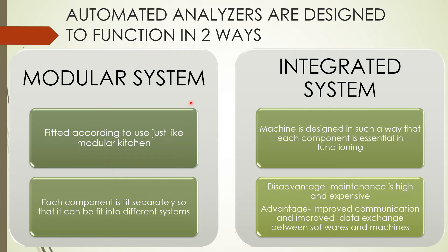Automated analyzers are designed to function in two ways: the modular system and the integrated system. The modular system is fitted according to use, just like a modular kitchen — each component is fitted separately so it can be incorporated into different systems. In the integrated system, the machine is designed such that each component is essential for functioning. Its maintenance cost is high and the instrument is expensive, but the advantage is improved communication and data exchange between softwares and the machine, allowing one person to operate and produce results.